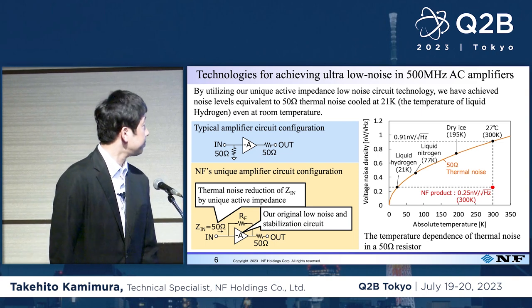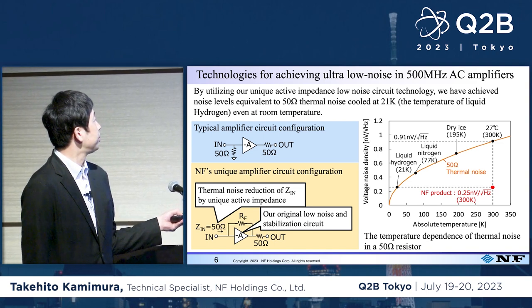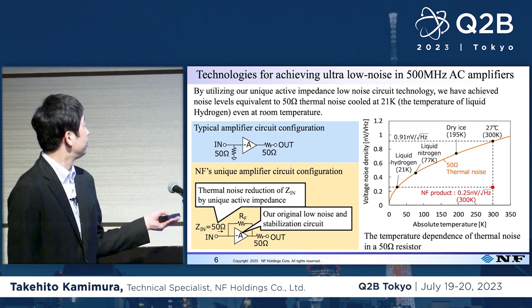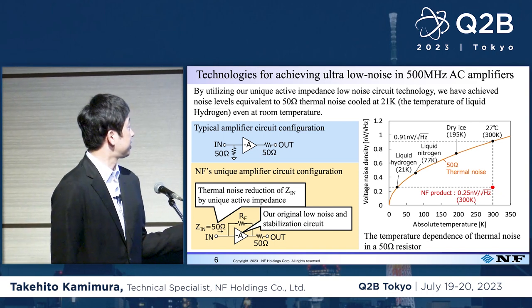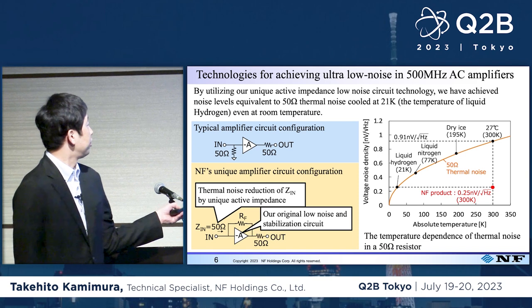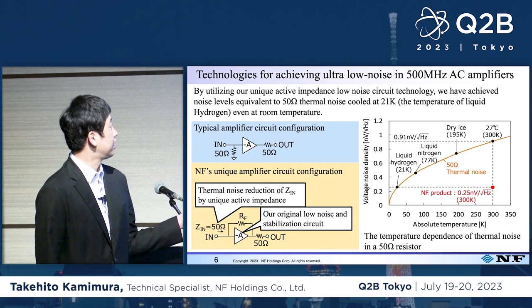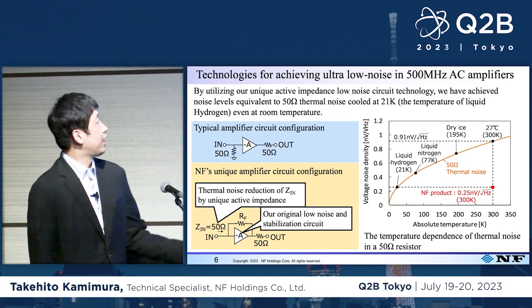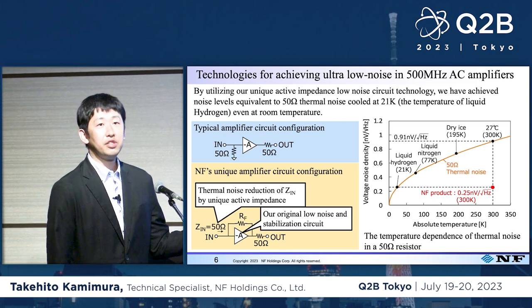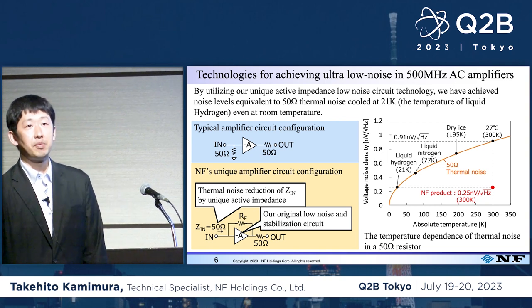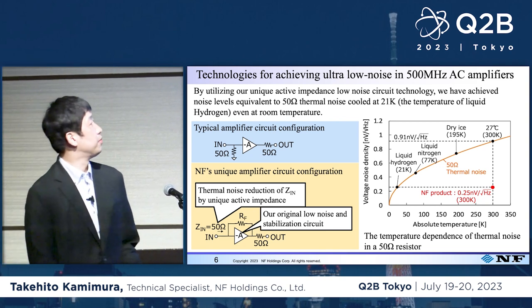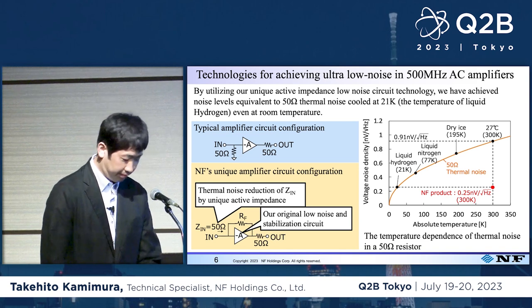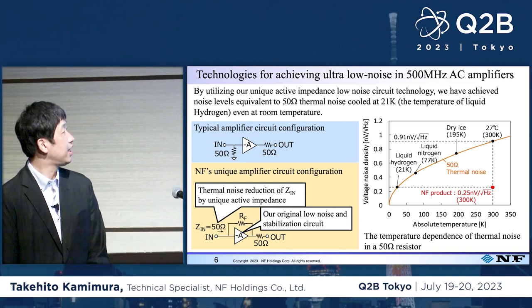For NF products, we use active impedance technology at the input. Therefore, we maintain the 50 ohm impedance while at the same time the thermal noise at the input can be lowered. The amp itself also has our own original low noise and stabilization technologies. With these technologies under room temperature, 0.25 nV/√Hz low noise can be achieved. Converting to the 50 ohm thermal noise equivalent, this level corresponds to the temperature of liquid hydrogen.